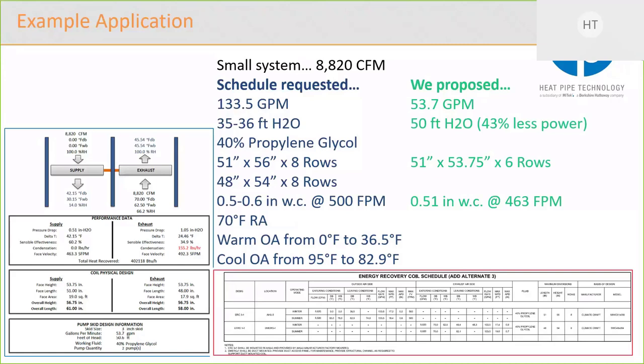So even though the schedule said 0.5 to 0.6 inches of water column drop, we actually knew that we were going to be getting 1.05. So when we provided that quote, we were able to educate the engineer to be thinking about the condensation he might get in his exhaust coil in the winter and maybe design for that extra pressure drop in the system.